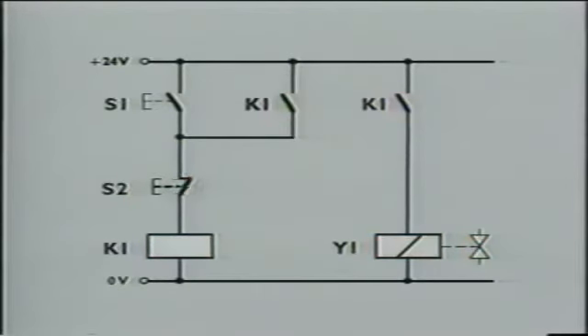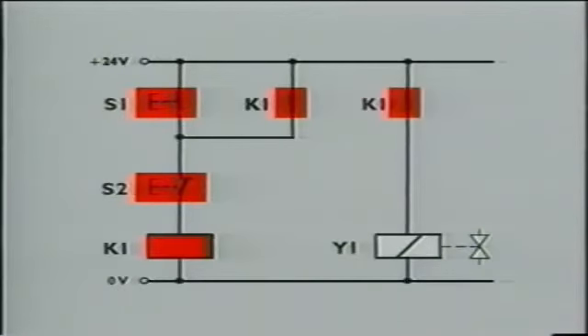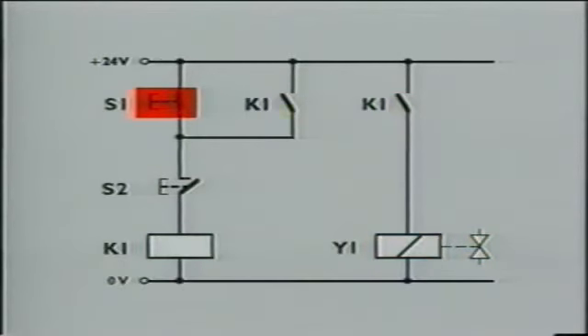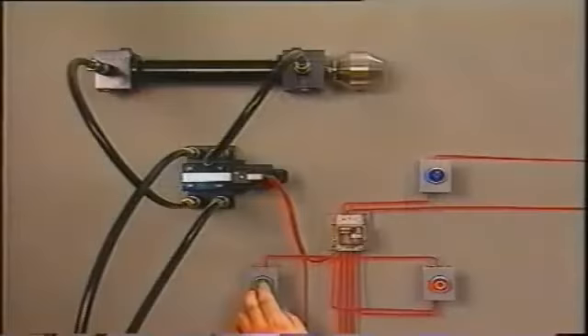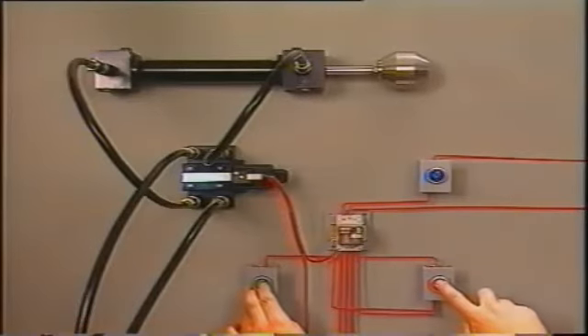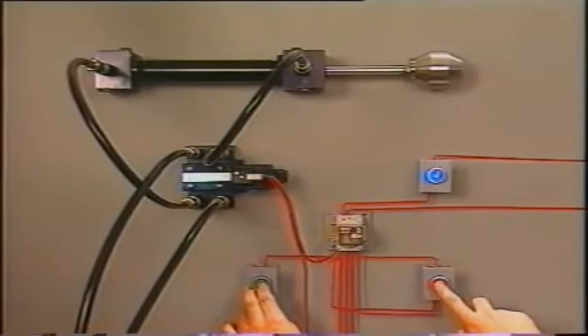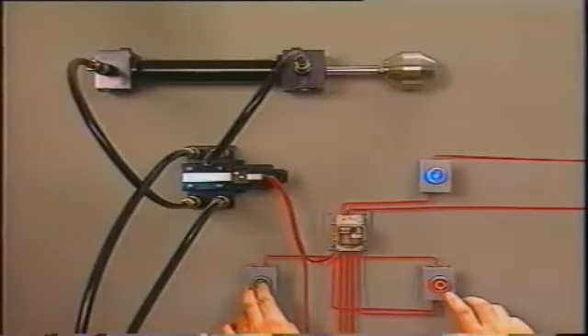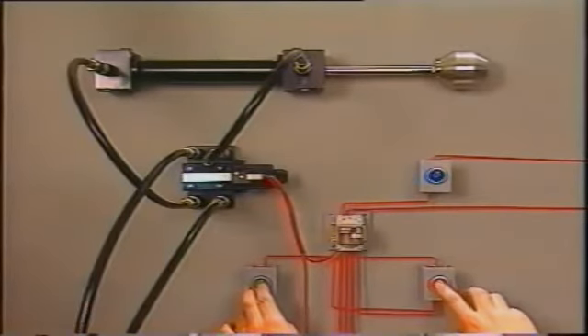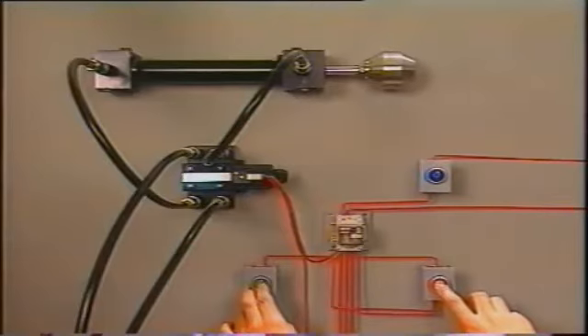This means that the circuit is interrupted if S2 is pressed, regardless of the position of S1. This is called a dominant OFF latch. Here, the cylinder retracts immediately if the OFF signal is given, even if the ON signal is still present. Machines may require this kind of latch for safety reasons.